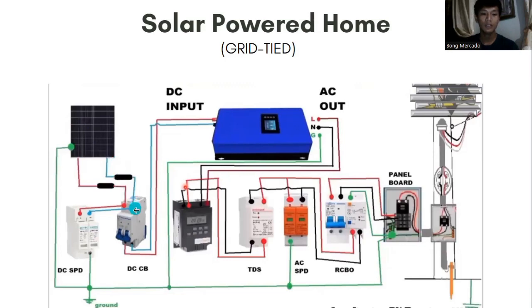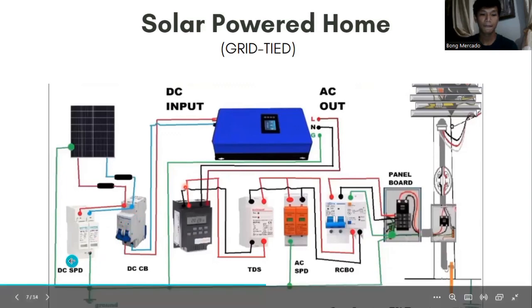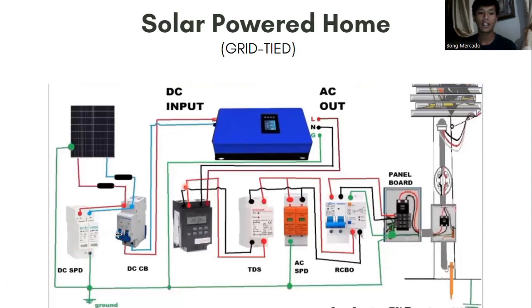And then, of course, being a DC circuit breaker, it has no polarity, the positive and the negative can be interchanged. So, next is we're going to connect the DC SPD in parallel to the input side of the DC circuit breaker. Ito. Which is labeled as positive and negative, being a direct current surge protection device. And this portion is routed to our grounding conductors, which is interconnected towards our grounding electrode.